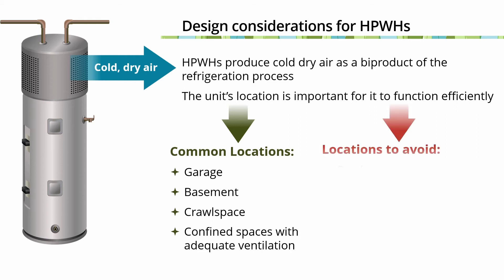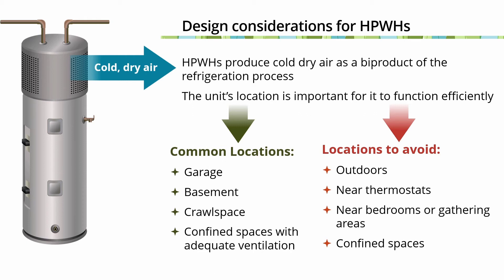Locations to avoid include placing a heat pump water heater outdoors, which may void the manufacturer's warranty if the unit is not designed for outdoor exposure. If placed in conditioned space, avoid locating it near thermostats used for space heating and cooling, which may result in improper heating or cooling of the home. Also avoid locating heat pump water heaters near bedrooms or gathering spaces to avoid noise. A closet or confined location is viable, but it's important to provide required clearances and sufficient supply and exhaust air per the manufacturer's requirements.